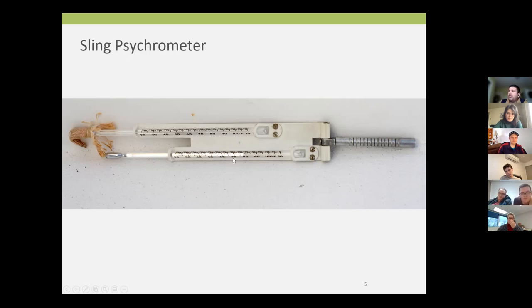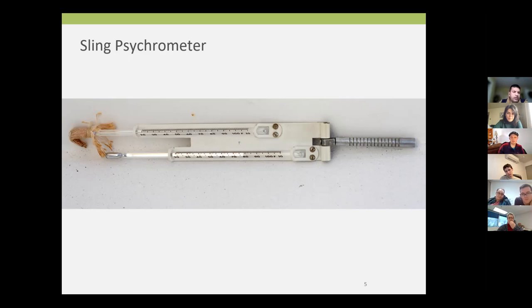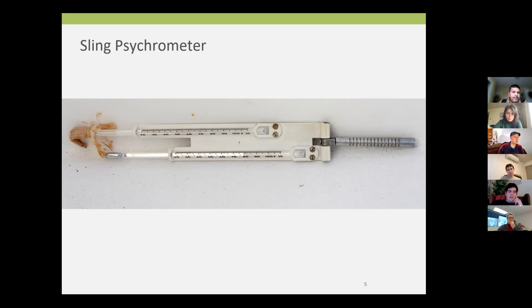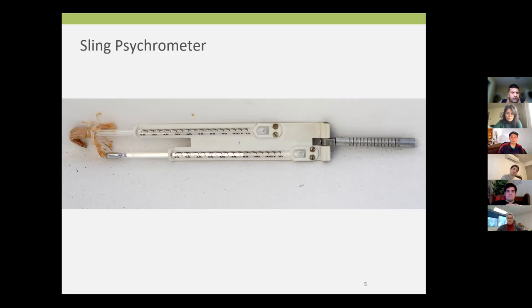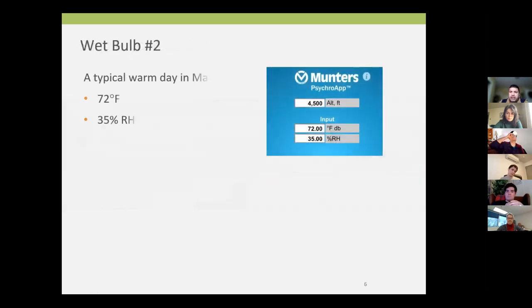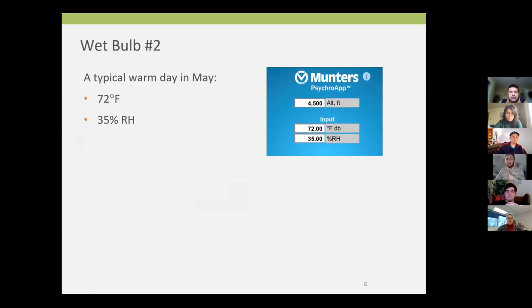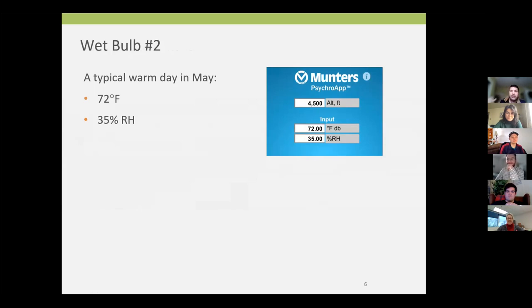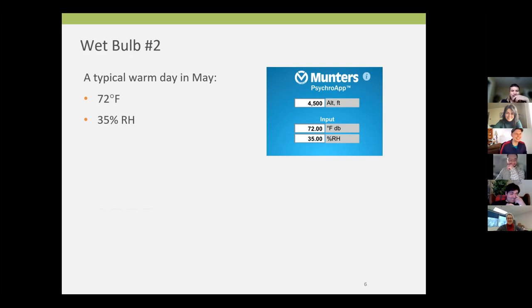Velocity. You're spinning it in the air, giving it velocity. And what you'll find is that you'll have a dry bulb reading, 80 or 90 degrees. You don't know the humidity, and you'll have the wet bulb temperature. And that's going to change from place to place. A lot of you have heard that evaporative cooling works in Utah, but doesn't work in Florida. Why does it not work in Florida? Humidity is too high. So cooling towers take advantage of that fact. In Utah, cooling tower is a lot better than it would be in Florida. That's a great way to reject heat.